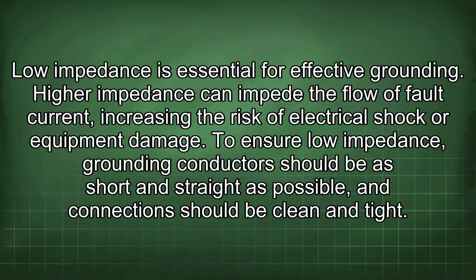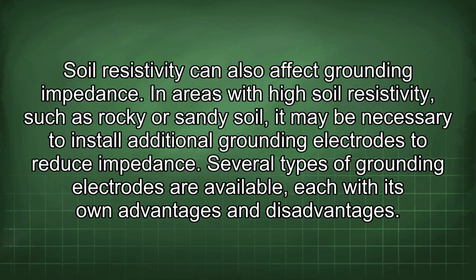To ensure low impedance, grounding conductors should be as short and straight as possible, and connections should be clean and tight. Soil resistivity can also affect grounding impedance. In areas with high soil resistivity, such as rocky or sandy soil, it may be necessary to install additional grounding electrodes to reduce impedance. Several types of grounding electrodes are available, each with its own advantages and disadvantages.